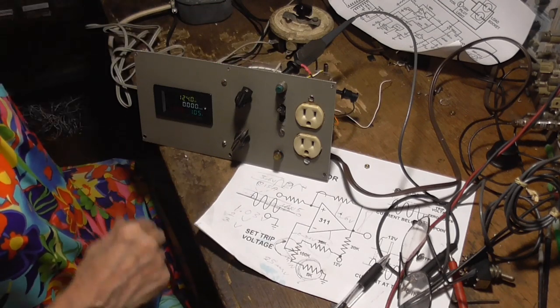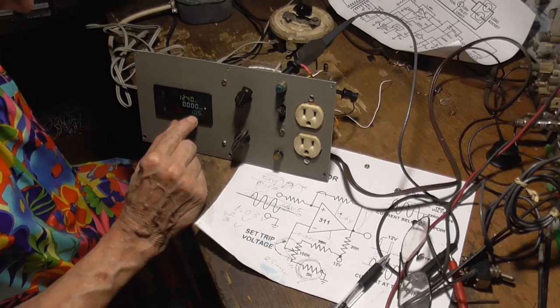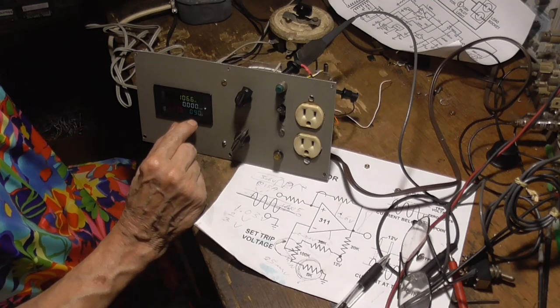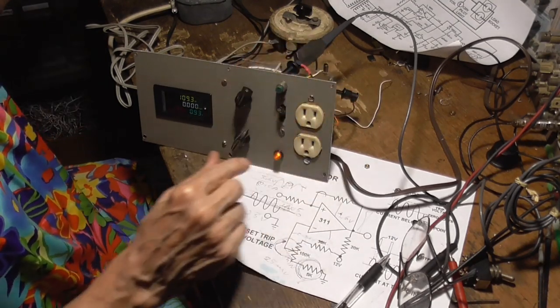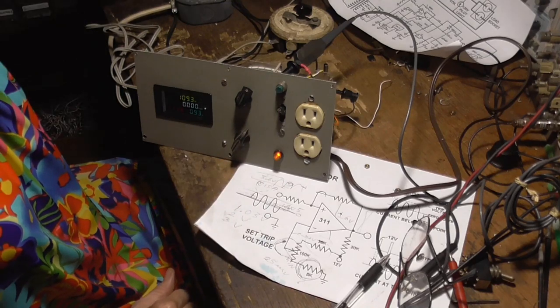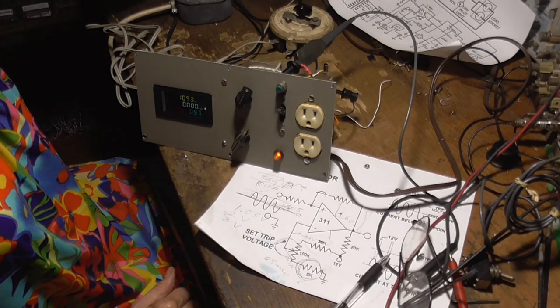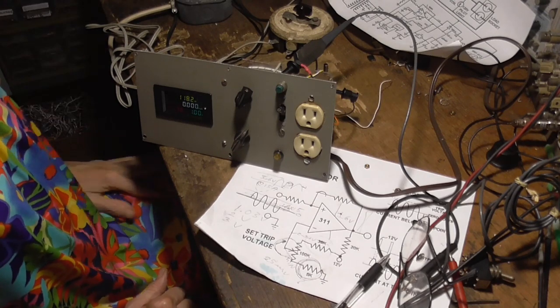So now I'm going to go below 1 amp, down to 0.9 amps. Okay, that's 0.9 amps. I'll reset it. Now I'm going to bring the current up to 1 amp and see if it triggers.